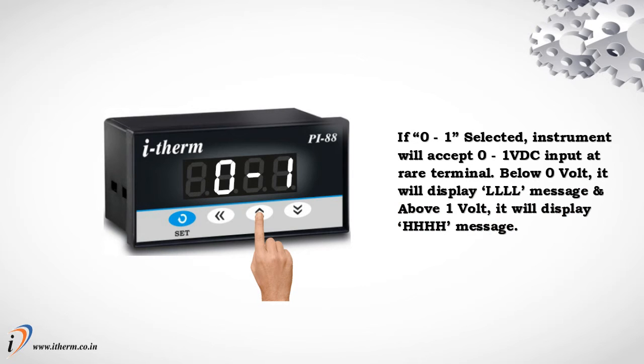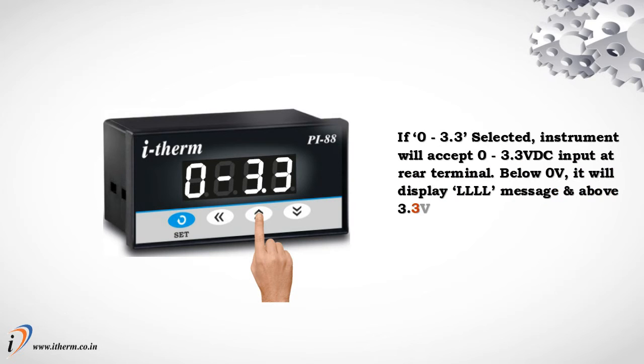Below 0 volt, it will display an LLLL message, and above 1 volt, it will display an HHHH message. If 0 to 3.3 is selected, the instrument will accept 0 to 3.3 volt DC input at the rear terminal. Below 0 volt, it will display an LLLL message, and above 3.3 volt, it will display an HHHH message.